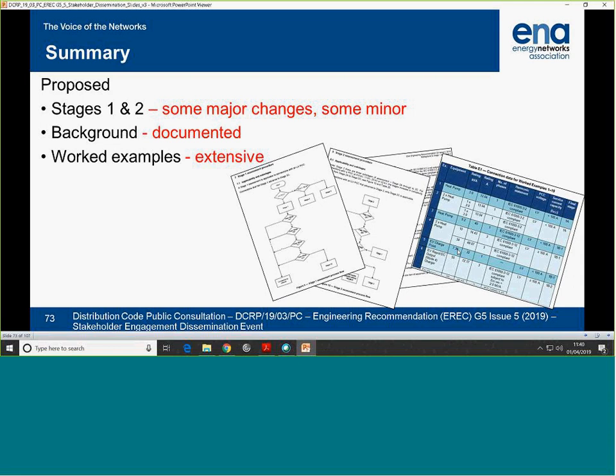The DNOs publish information in the long-term development statement. That has the fault level at the source bars, down to 11 kV. Generally it's about switching and that's as far as it goes, so it has the top fault level. Then when we get the application, they say, if this transformer's out and that circuit's out and these generators are off, the minimum fault level is this, and it's a tiny fraction of what's typically in the LDS. So it's much more onerous what we'll have to design to in practice.